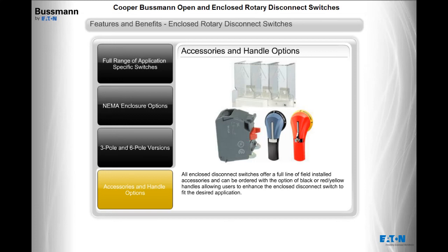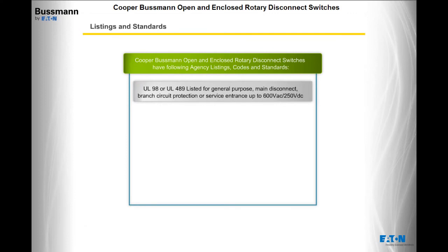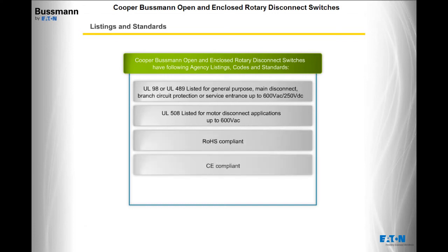Enclosed disconnect switches can be ordered with the option of black or red and yellow handles, allowing users to enhance the enclosed disconnect switch to fit the desired application. Cooper Bussmann open and enclosed rotary disconnect switches carry the following agency listings: UL98 or UL489 listed for general purpose, main disconnect, branch circuit protection, or service entrance up to 600 volts AC and 250 volts DC; UL508 listed for motor disconnect applications up to 600 volts AC; and are RoHS compliant, CE compliant, and IEC compliant.